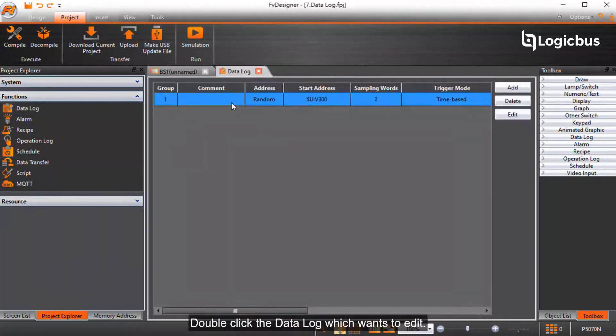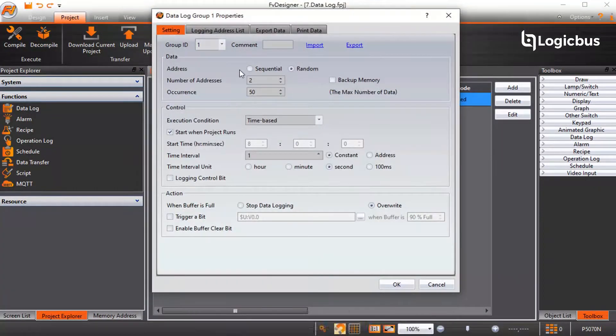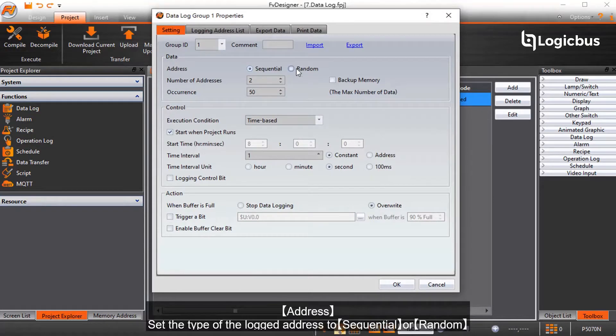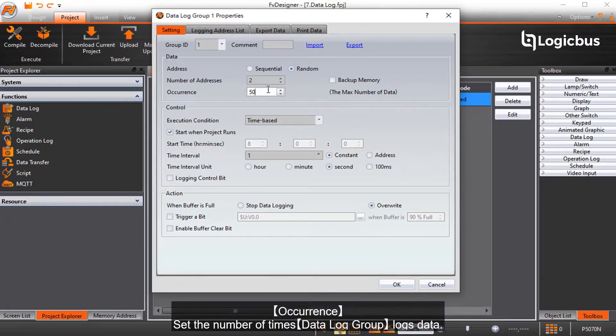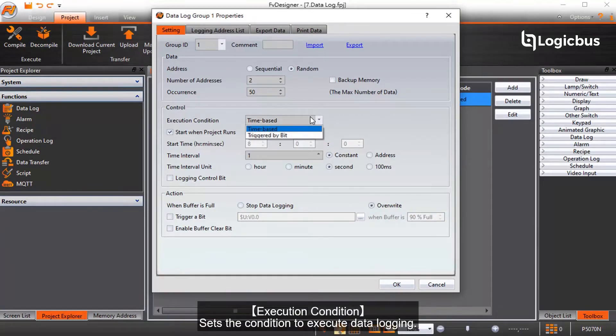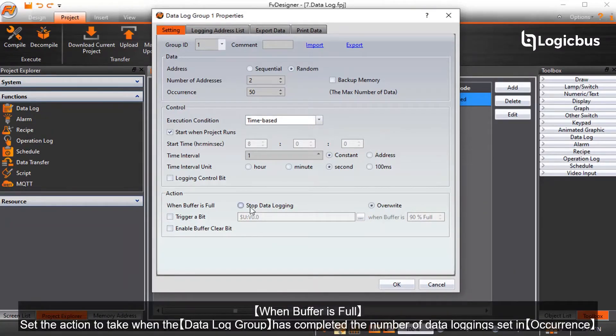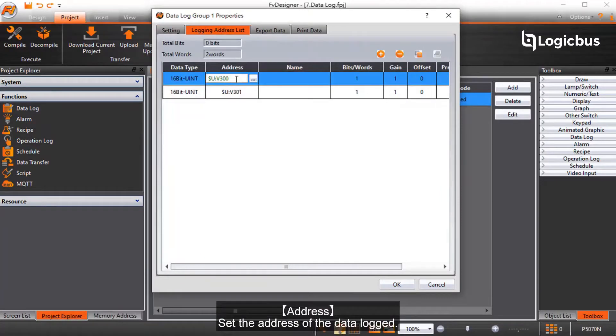Select data log and double-click the data log you want to edit. Set the type of the log address to sequential or random. Set the number of addresses for the data log group. Set the log occurrence — the number of times the data log group logs data. Set the execution condition to execute data logging. When the buffer is full, set the action to take when the data log group has completed the number of data logging set in occurrence.